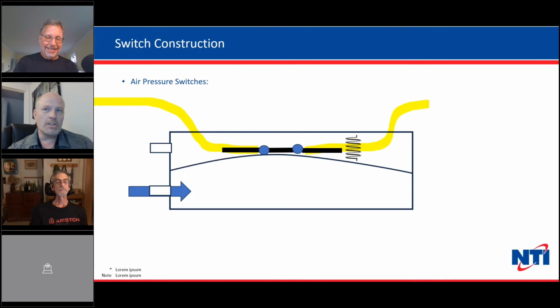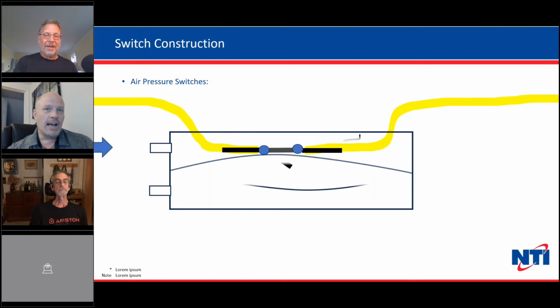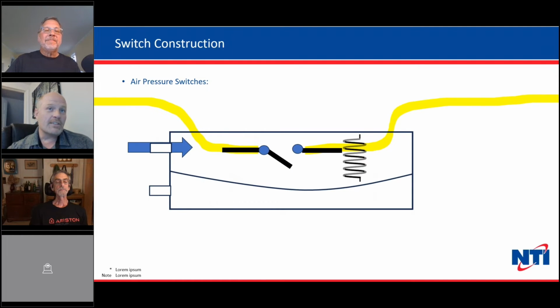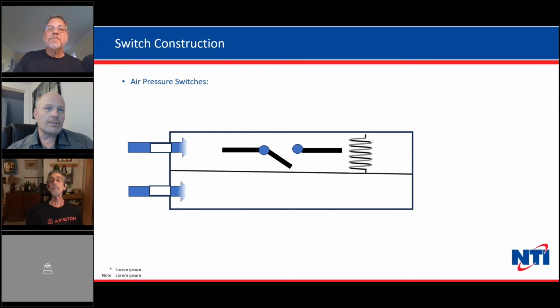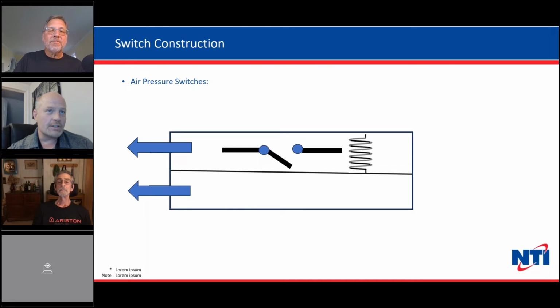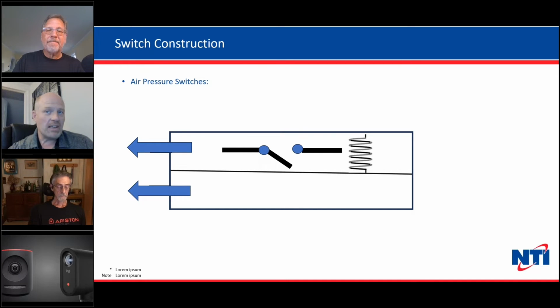So again, same thing, you blow into the bottom, it'll trip the switch. If you blow into the top, you deactivate the switch. And when it's used in the dual port configuration, if you provide equal pressure, top and bottom, whether it's suction or pressure, the switch does nothing because the pressure difference between top and bottom is 0, which means the diaphragm sees no net movement one way or the other, and the switch will remain and not do anything.